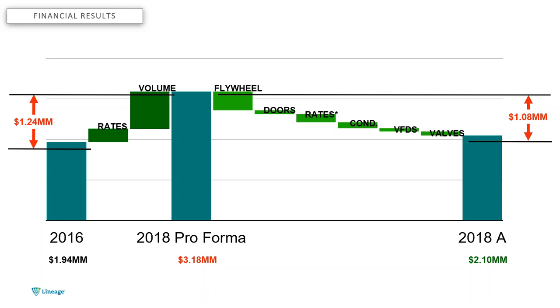But due to the flywheeling technique, along with other things like hardware upgrades—we replaced doors, changed the rate schedule to direct access, put in new condensers, VFDs, and motorized valves on the refrigeration system—we saved $1 million a year at this facility. I don't have time to get into all of those details, but now we're scaling it throughout the portfolio.